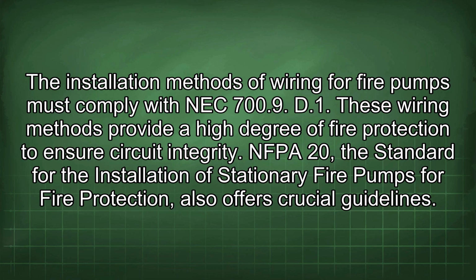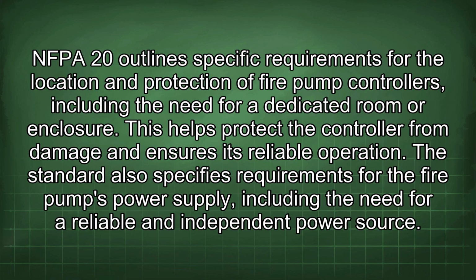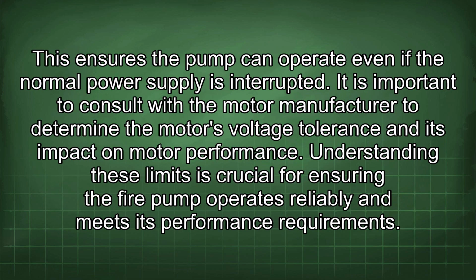NFPA 20, the standard for the installation of stationary fire pumps for fire protection, also offers crucial guidelines. NFPA 20 outlines specific requirements for the location and protection of fire pump controllers, including the need for a dedicated room or enclosure. This helps protect the controller from damage and ensures its reliable operation. The standard also specifies requirements for the fire pump's power supply, including the need for a reliable and independent power source. This ensures the pump can operate even if the normal power supply is interrupted.